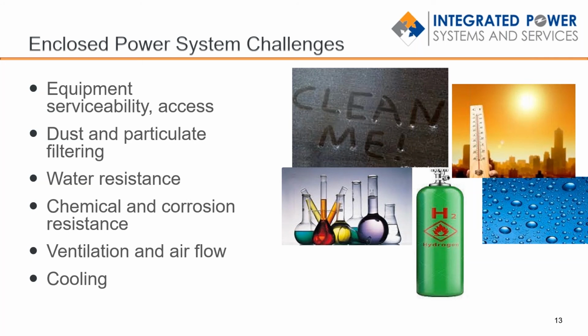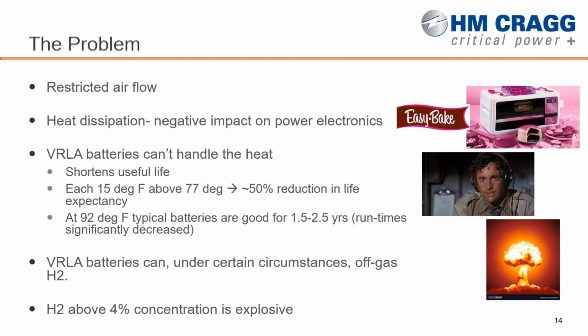And as we talk about this next slide here, the big problem when we stick a UPS, whether it's a small 2U single phase UPS or one of the larger Eaton 93 PMs, into an enclosure, think of it as skin over skin, we have the potential of restricting airflow, and that's going to have an impact on how we dissipate heat. And as you all know, as professionals in the power quality industry, heat is not a good thing. It's not a good thing for the power electronics, and it's more specifically not a good thing for batteries.